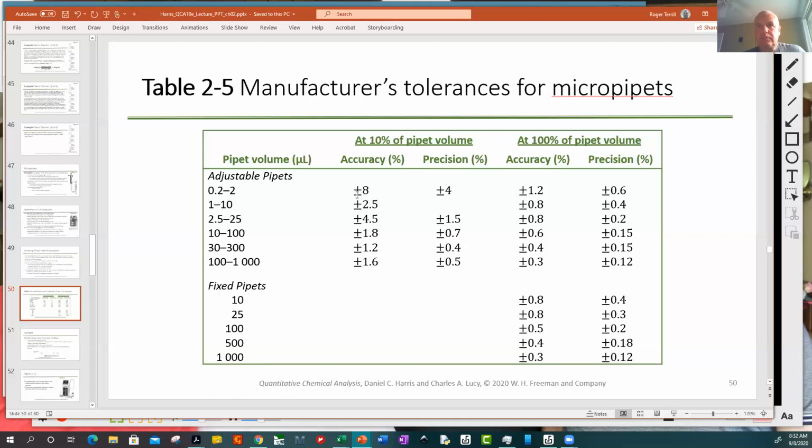So accuracy, if you have a sensitive balance, you can compensate for this. Right? You just weigh water first. You record the temperature, the nominal volume of water, say 10 ml, the actual mass of water, use the density to get the actual volume of water. And you can correct for this value. Right? But then you can never correct for this part here.